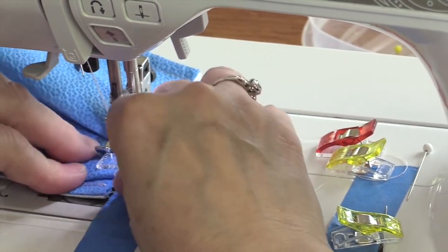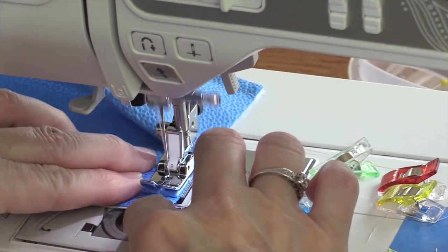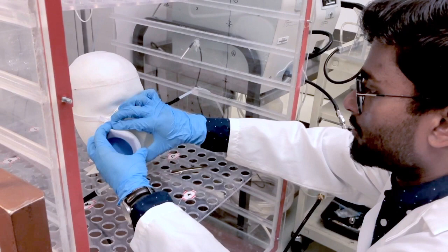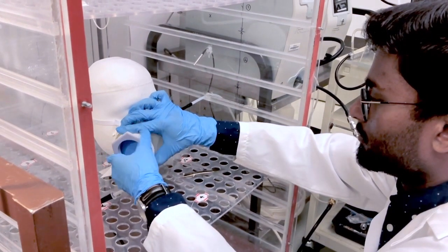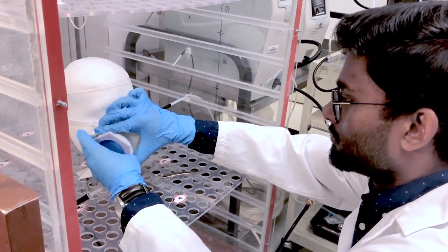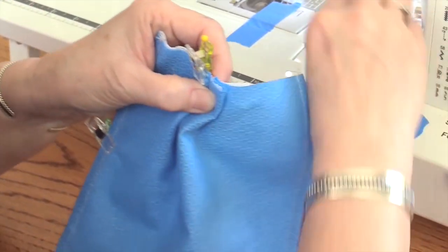This is a halyard fabric — a medical-grade fabric cloth used for hospital gowns or sterilization wraps. Two layers of this medical-grade fabric have a maximum filtration efficiency of about 80%. However, the most penetrating particle size of the virus can lower its efficiency to about 45%.